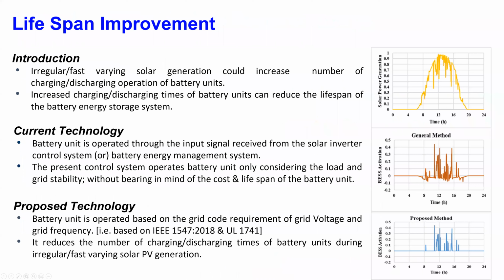We also design algorithms to extend the life of the battery systems. Basically, we propose different charge rates based on aging studies—not 100% duty, we maintain duty at 80%, and we maintain the discharge rate lower, for example 0.5C or less. This way, you can be sure the system has a longer service life.